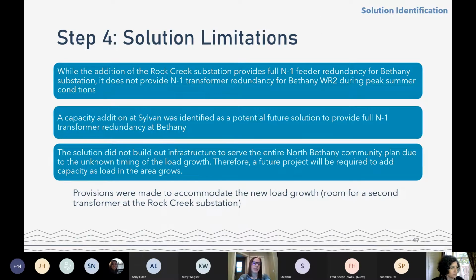Some solution limitations we found: while that substation provided full N-1 feeder redundancy for Bethany, it did not provide full N-1 transformer redundancy for one of the transformers during peak summer conditions. Transformer redundancy can be harder to achieve. We did identify that a capacity addition at Sylvan could be a potential future solution to provide full N-1 transformer redundancy at Bethany. The solution didn't build out infrastructure to serve the entire North Bethany community plan. We don't always know the exact timing, but we made provisions to accommodate future load growth with room for a second transformer at Rock Creek Substation.